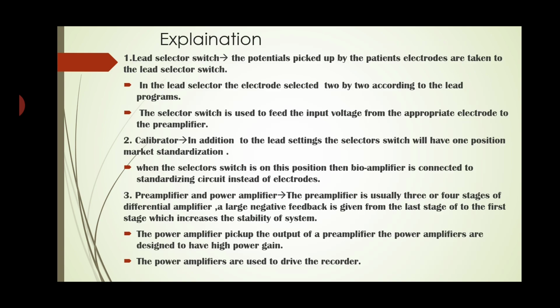First, the lead selector switch. The potential picked up by the patient electrodes is taken to the lead selector switch. In the lead selector, the electrodes are selected two by two according to the lead programs. The selector switch is used to feed the input voltage from the appropriate electrode to the preamplifier.